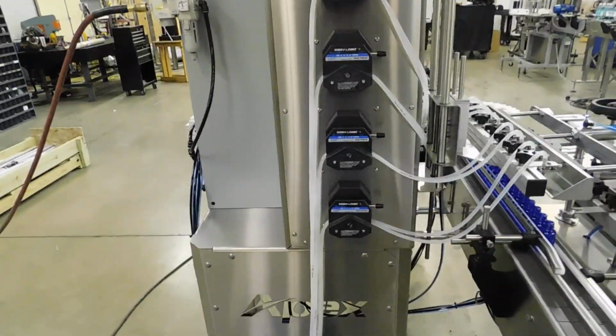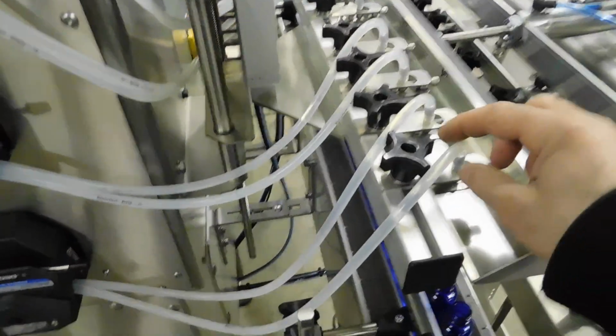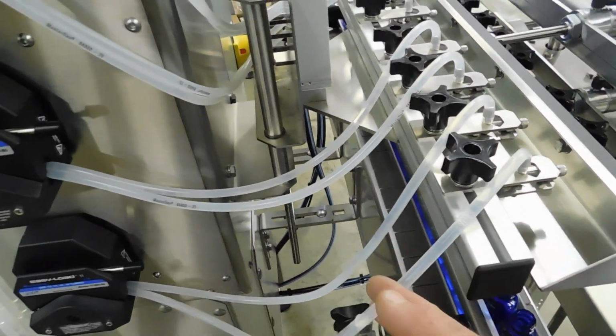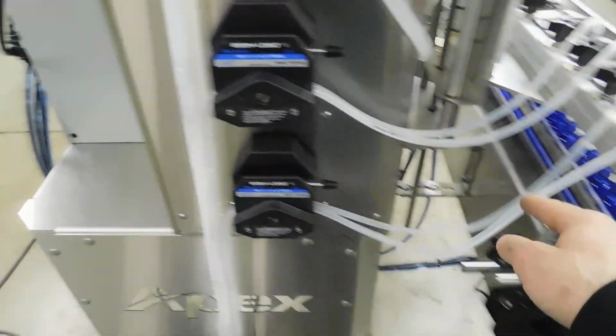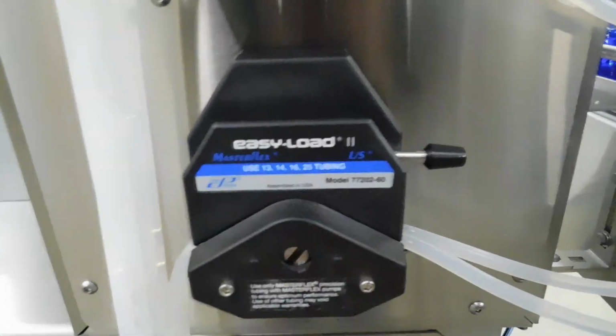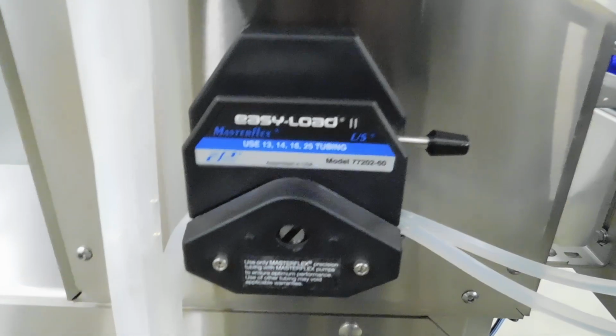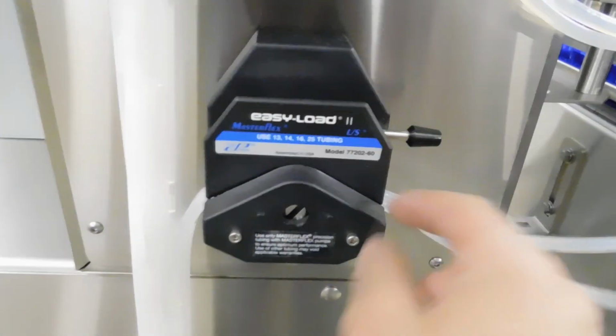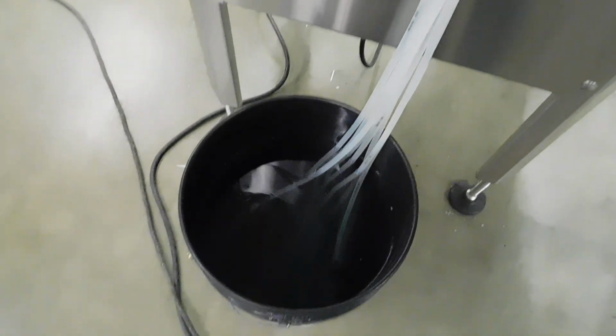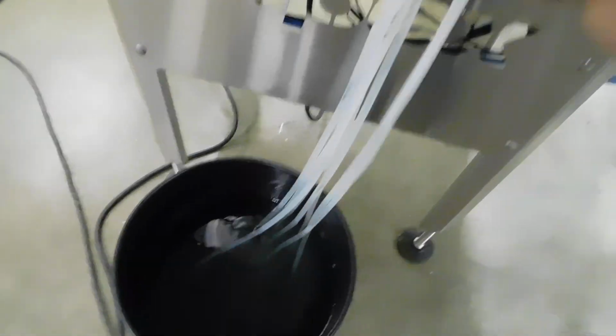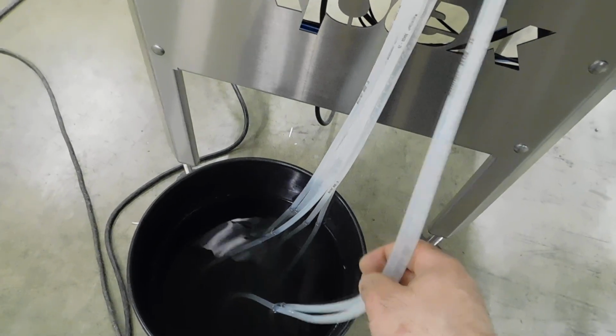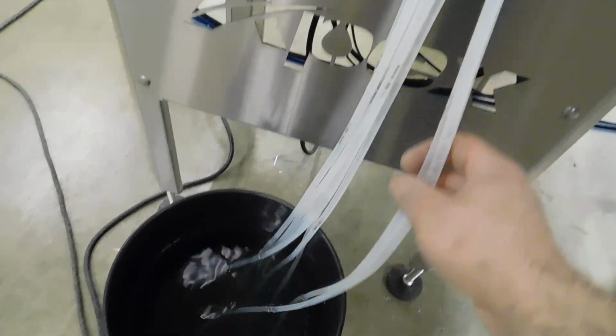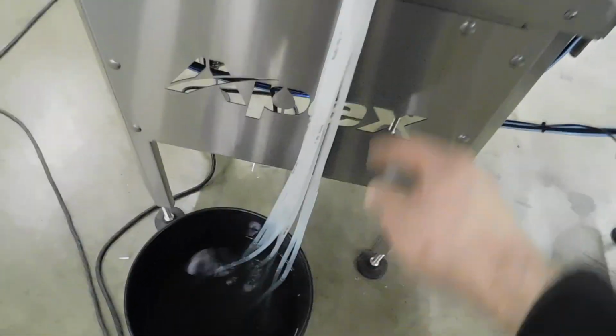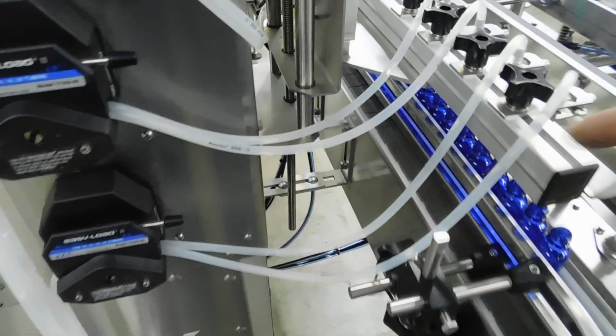Now we will look at the tubing for the peristaltic pumps. Each fill head has a tube connected to it. This tube runs back to a Masterflex Easy Load peristaltic pump head. These tubes pass through the pump head and into our product. You want to try to maintain the tubing length of each pump the same. So the length of each tube going through the pumps should be the same.